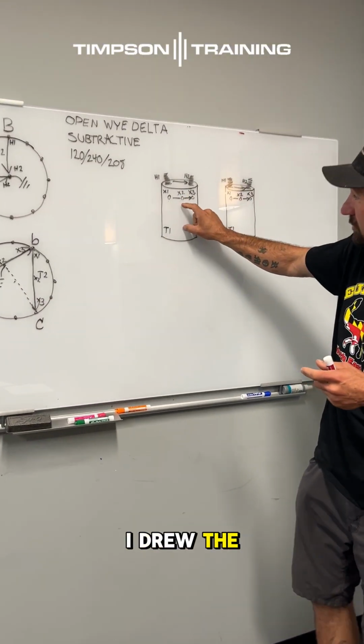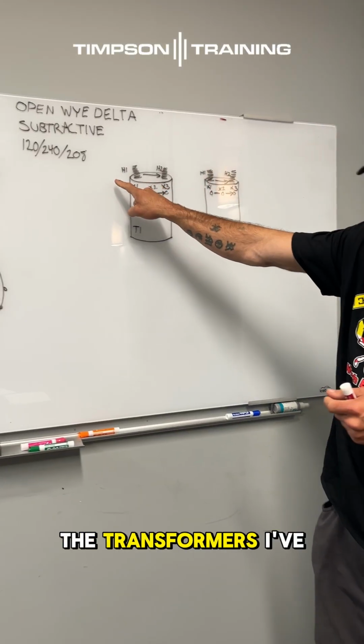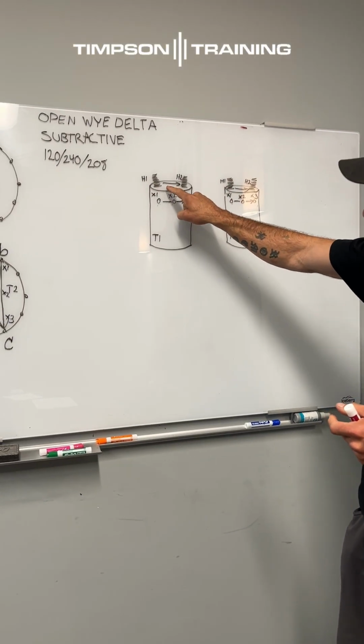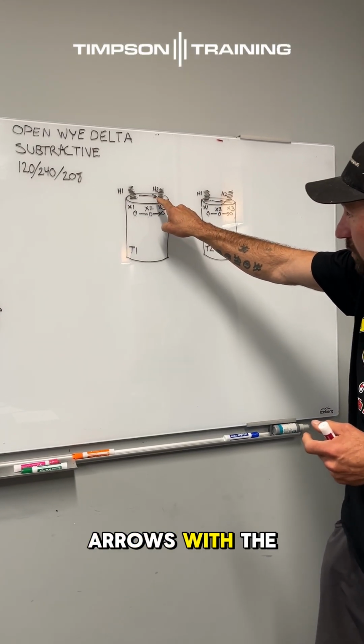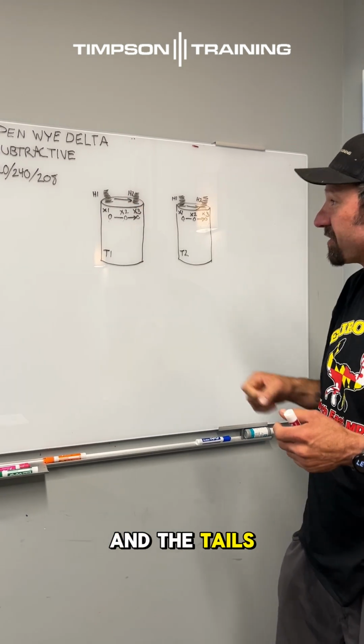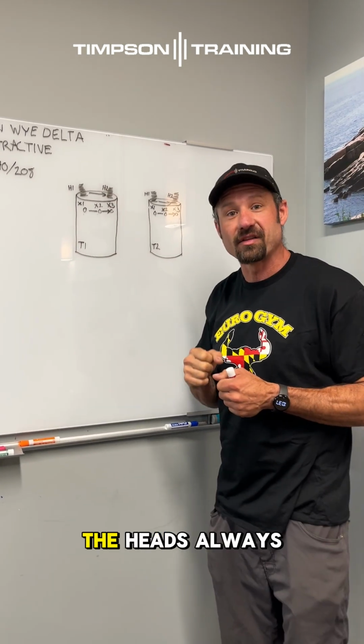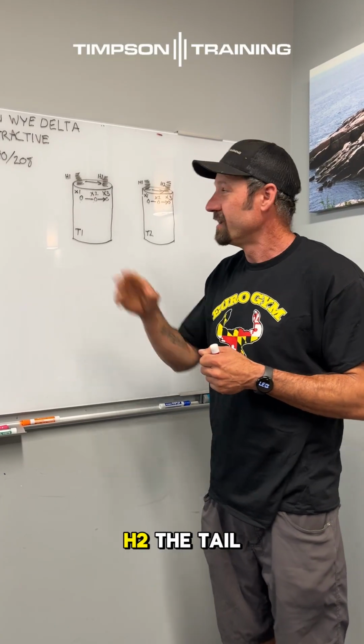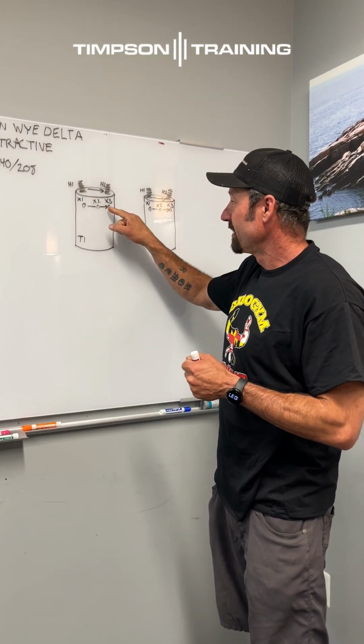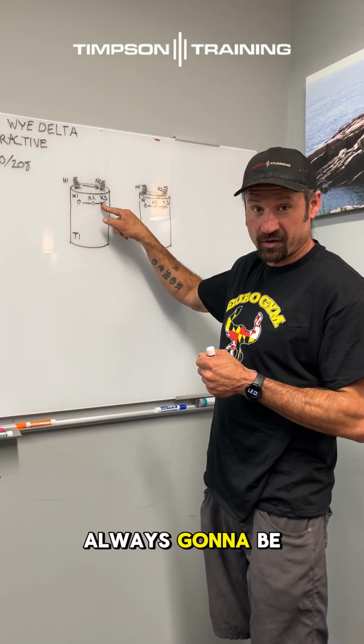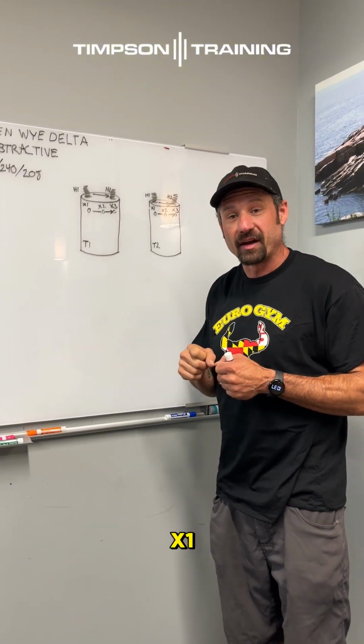And you see I drew the transformers here, and on the transformers I've labeled everything, including drawing the arrows with the heads and the tails. Now when we look at the heads and the tails, the head's always going to be on H2, the tail on H1. For your secondary, the head's always going to be on X3 and your tail on X1.